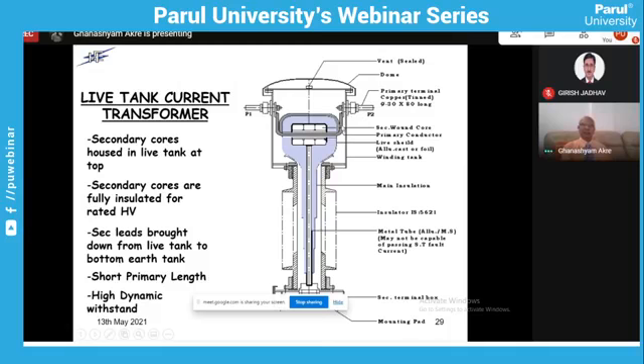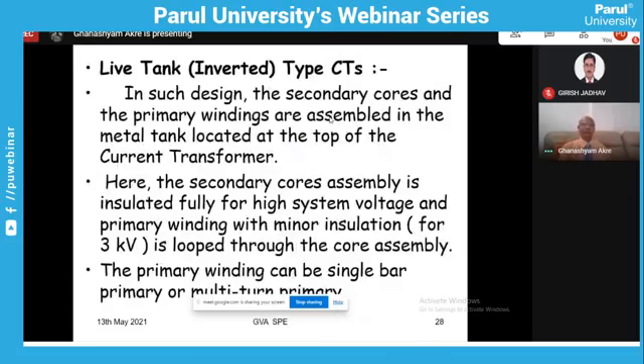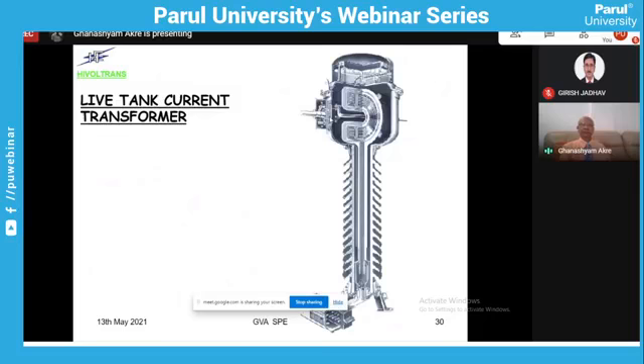So essentially here you have to insulate the cores and secondary, and that is why you see the cores are insulated and then they are inserted here, and the primary is only looped through it. This is called live tank because the cores are lying in the tank which is live at high potential, and that is why it is live. The principle of operation, that is the magnetic circuit and primary to secondary, is the same in all cases, but from a construction point of view they are different. You can see the cross section of this live tank design.